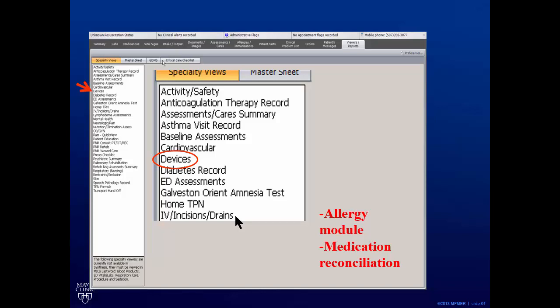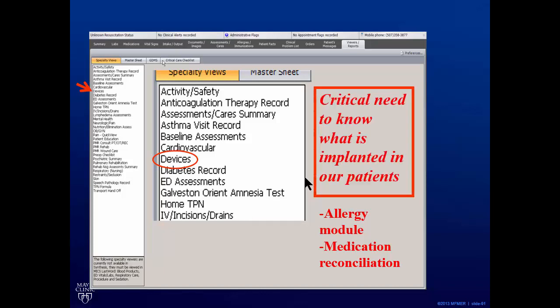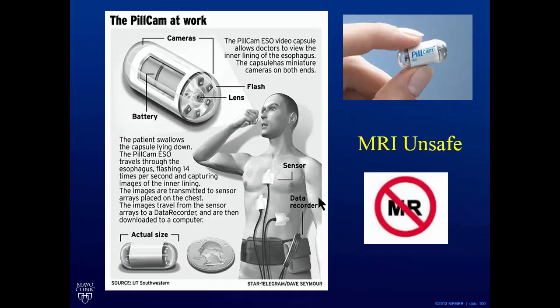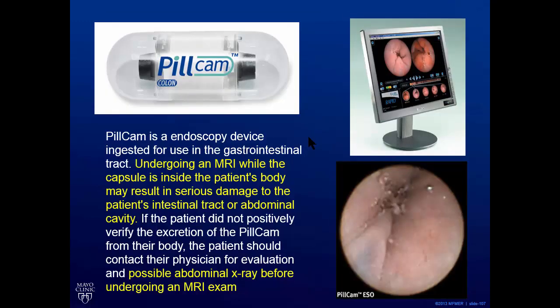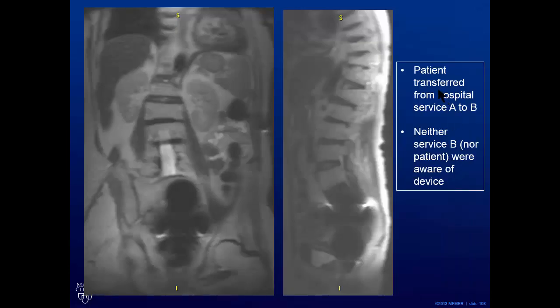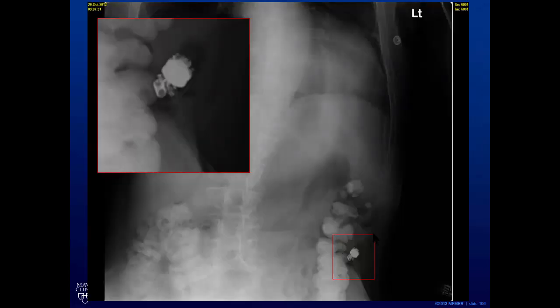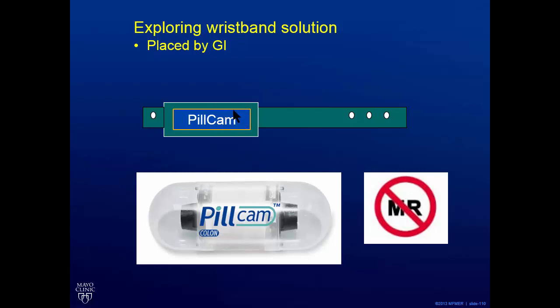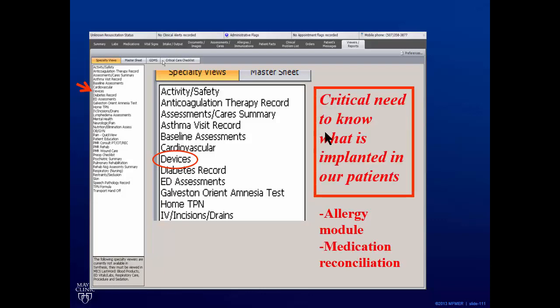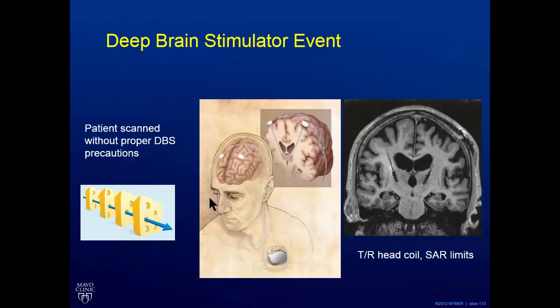We can make the case that tracking implanted devices is as important as allergies and medication reconciliation. We had a similar event with a pill cam — these are MRI unsafe. The patient was transferred from hospital service A to hospital service B, and neither service nor the patient knew the pill cam was still in them. The patient came down to MRI, we saw a tremendous blowout, and realized after reconstructing events that the pill cam had not exited the patient. We're exploring a wristband solution and working on getting something in the electronic medical record about implanted devices.